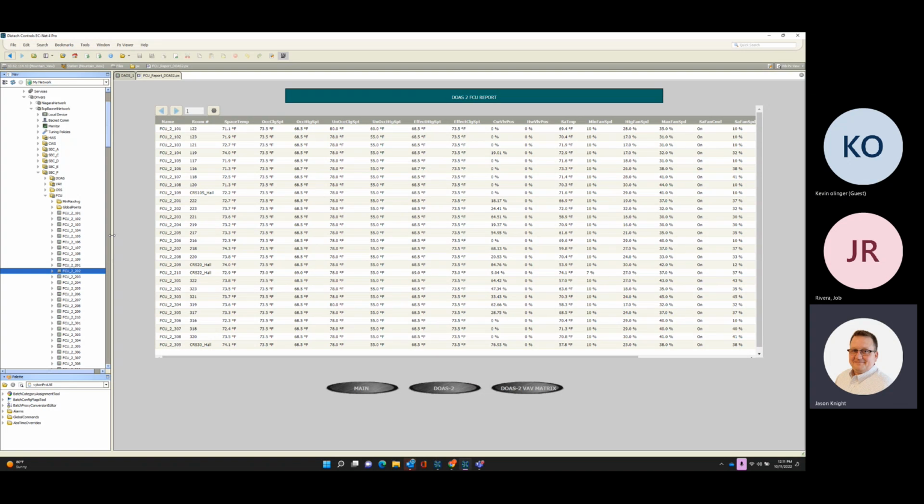It's the small industrial computer with cooling fins on it. There's no display, no nothing. It's just basically a box. Yep. And it has so much more computing power and hardware than a standard Niagara Jace. A standard Niagara Jace wouldn't be able to handle the communication load that you have going on in this campus. I don't want to call it a building because it's a campus.